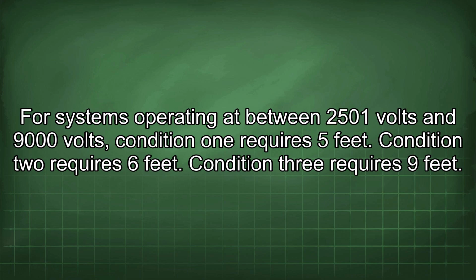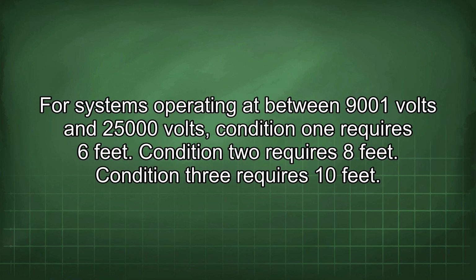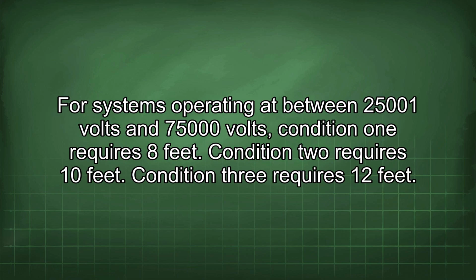For systems operating at between 2501 volts and 9000 volts, Condition 1 requires 5 feet. Condition 2 requires 6 feet. Condition 3 requires 9 feet. For systems operating at between 9001 volts and 25,000 volts, Condition 1 requires 6 feet. Condition 2 requires 8 feet. Condition 3 requires 10 feet. For systems operating at between 25,001 volts and 75,000 volts, Condition 1 requires 8 feet. Condition 2 requires 10 feet. Condition 3 requires 12 feet.